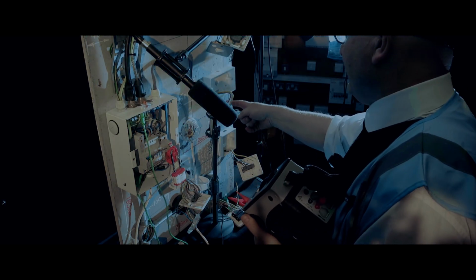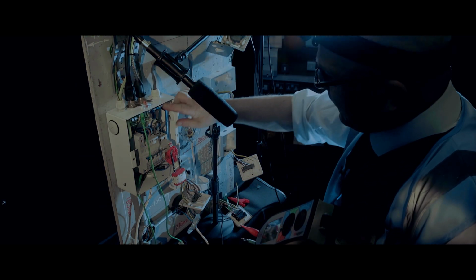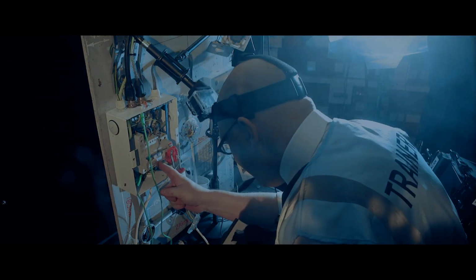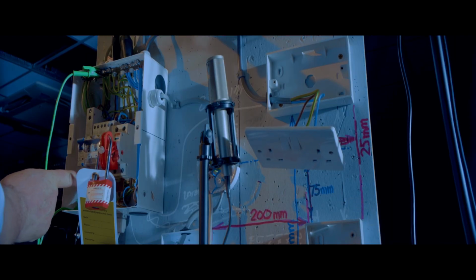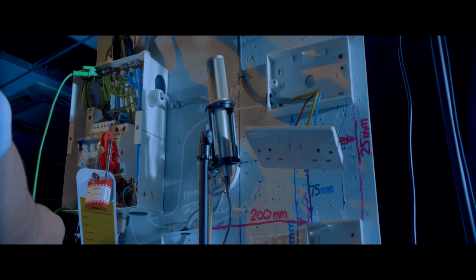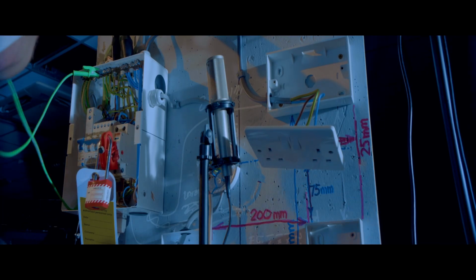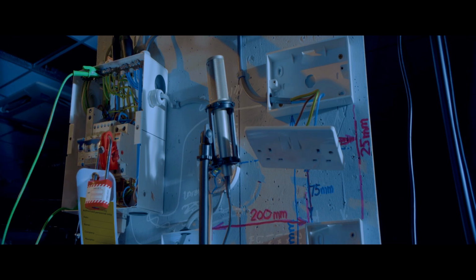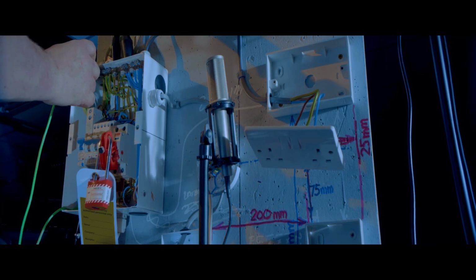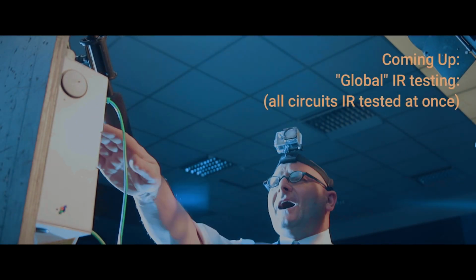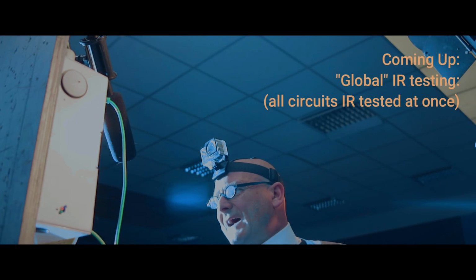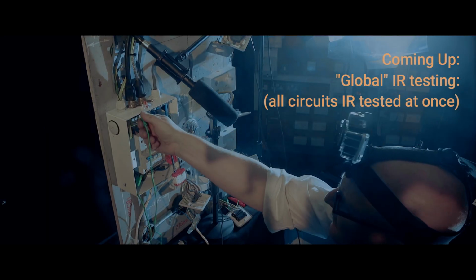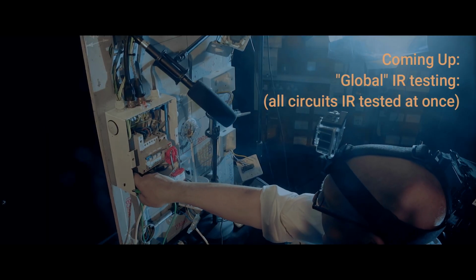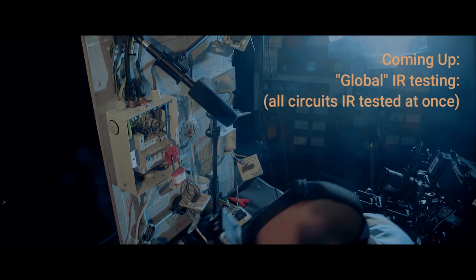So the DC current goes down the line all the way through the overcurrent protective device to the bus bar, which is connected via the link lead through the bus bar up to the CPC, up through the earth bar, and then from the CPC all the way back out to the socket. So we get a circuit. Now, that is another way to carry out your R1, R2 tests.